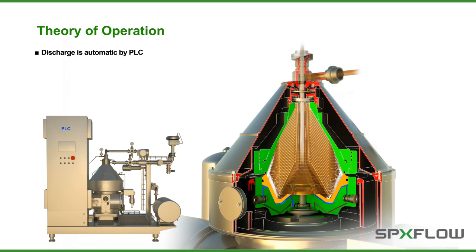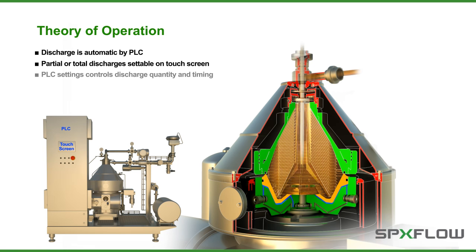Various automatic independent working cycles may be selected to perform partial and or total discharges during the separation and clean-in-place functions. Using settings within the PLC, it is possible to regulate the discharge quantity, time between discharges, and the combination between partial and total discharges.